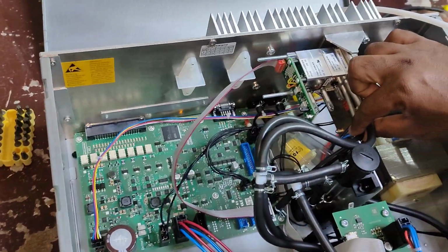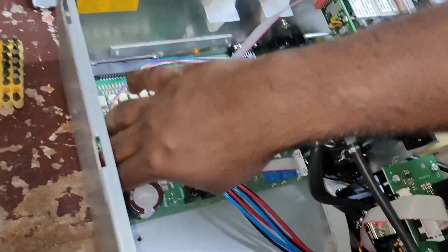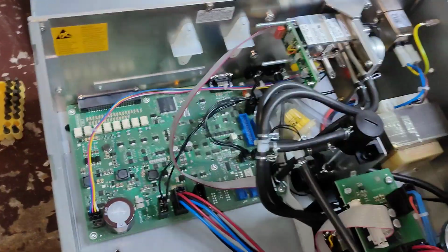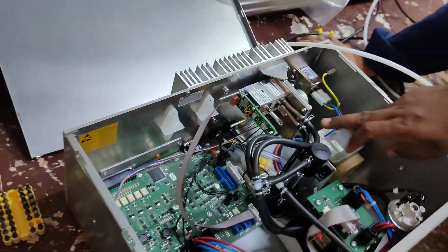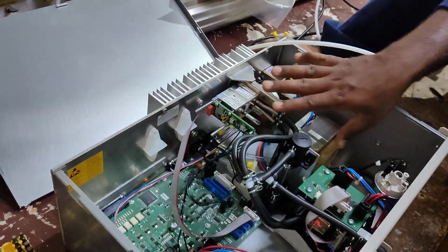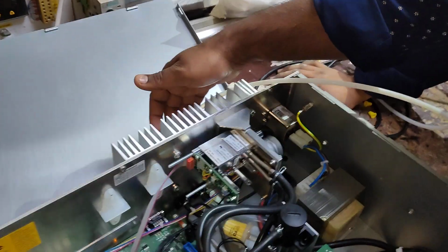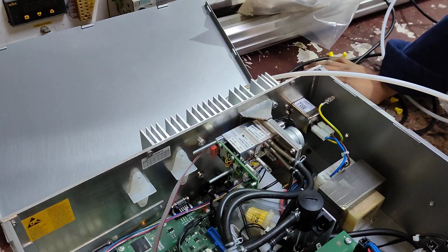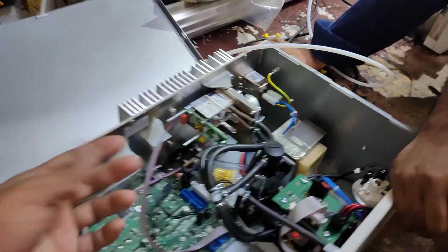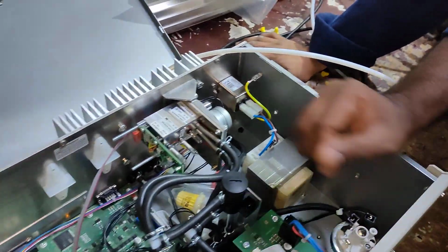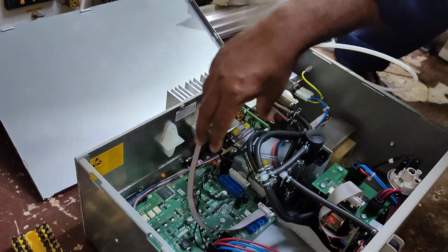So 2 sample in and 2 sample out. Then one detector signal, chopper motor signal, IR source signal. So 3 electrical, 2 pneumatic sample. Once you do this, only then go for removing the screws. Then take the whole body out. Then we can remove this one and this one, etc. So this chopper, 2 screws, you can remove and take the detector out.